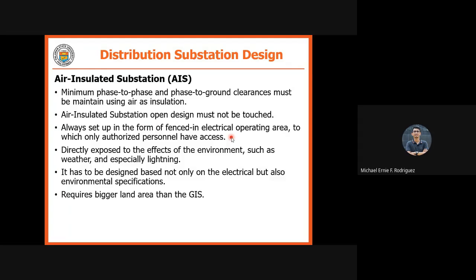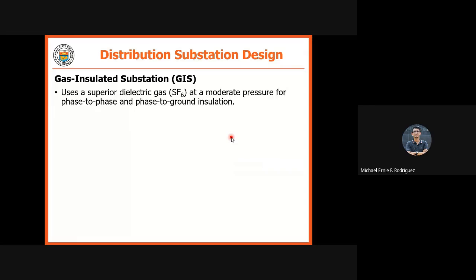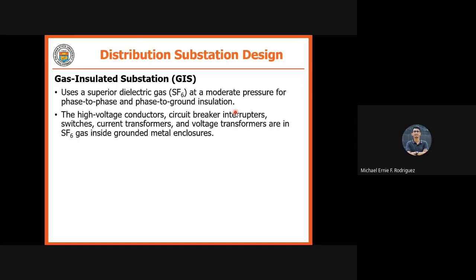And then another point for AIS: AIS requires a bigger land area than the GIS. Okay? So the area of an AIS is very large compared to a GIS. Now, GIS. The GIS, or gas insulated substation, uses a superior dielectric gas, which is SF6, at moderate pressure for phase-to-phase and phase-to-ground insulation. SF6 is sulfur hexafluoride. Okay? Sulfur hexafluoride. The high voltage conductors, circuit breaker interrupters, switches, CTs, and PTs are in SF6 gas inside a grounded metal enclosure. So you have SF6 gas, and your conductors, breakers, and equipment are in the SF6 gas.